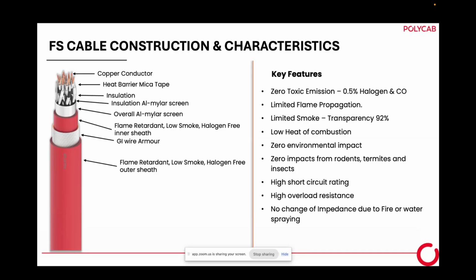So these cables are available with key features: zero toxic emission. We said zero toxicity, but in testing we did not find it to be zero. It is always lower than 0.5%. And the standard has set a limit of 0.5% for halogen and carbon monoxide. Then limited flame propagation: when we burn this cable in the laboratory and then remove the burner, it burns a certain length, and we check the balance length, the unburnt area, how much it is. That falls into the specification. If it meets, then it complies.